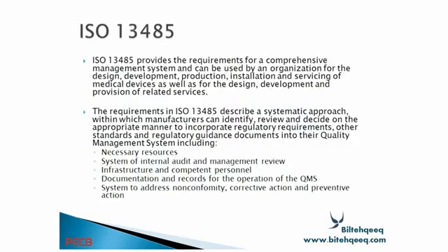Basically, ISO 13485 provides the requirements for a comprehensive management system and can be used by an organization for the design, development, production, installation, and servicing of medical devices, as well as for the design, development, and provision of related services.